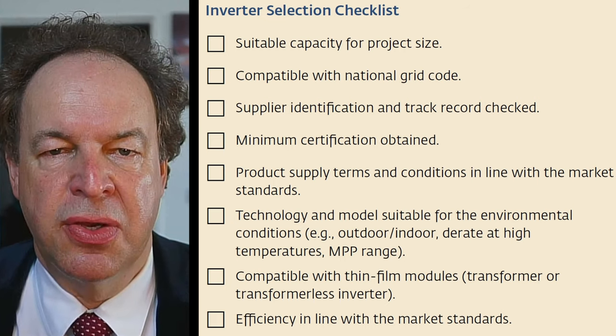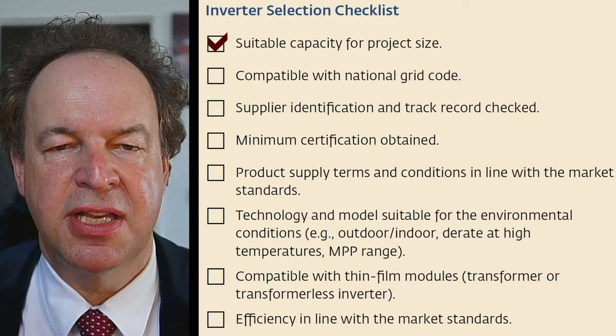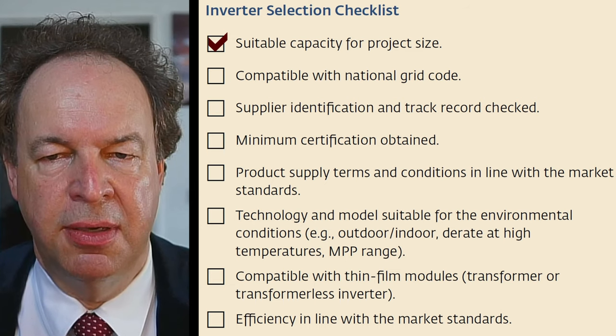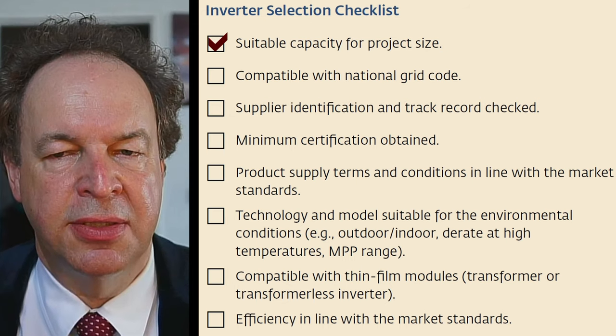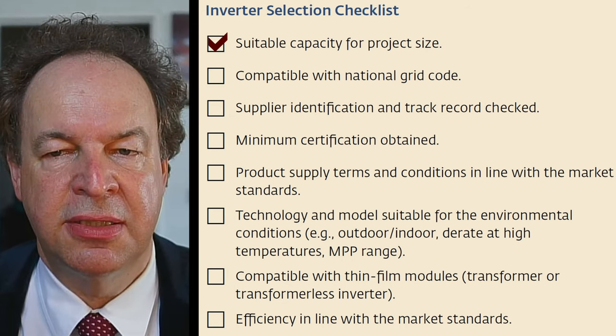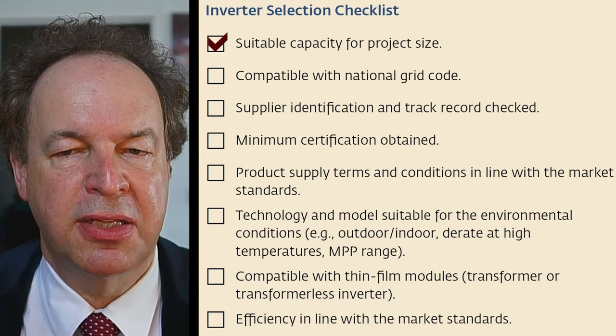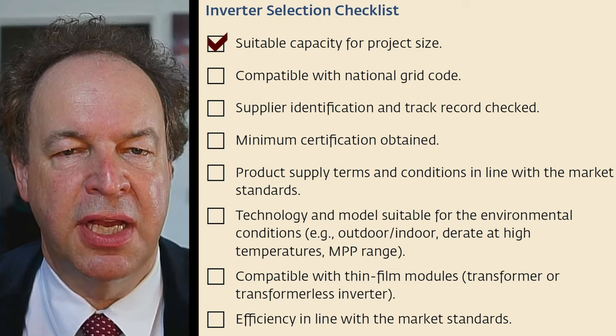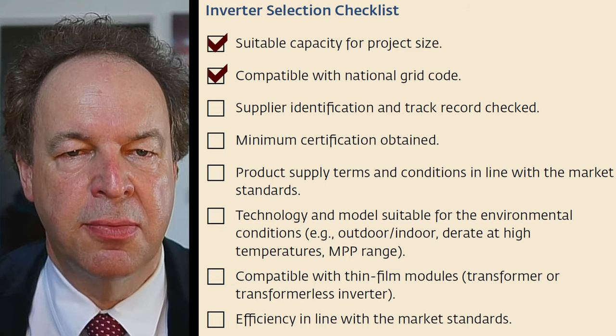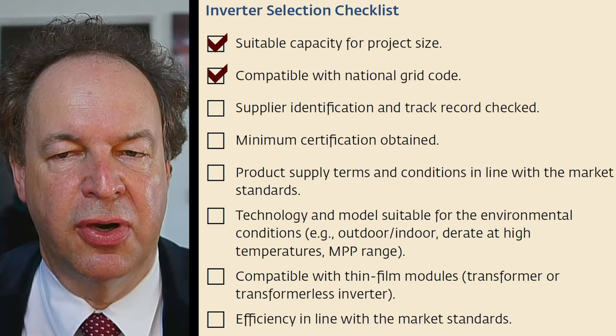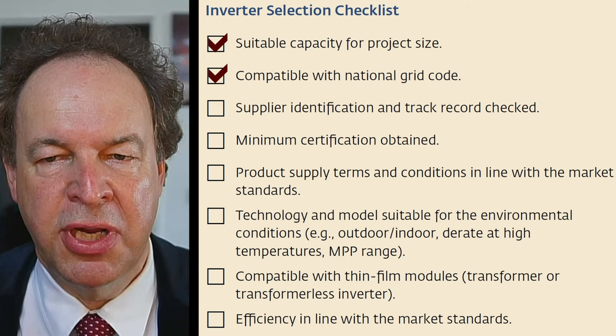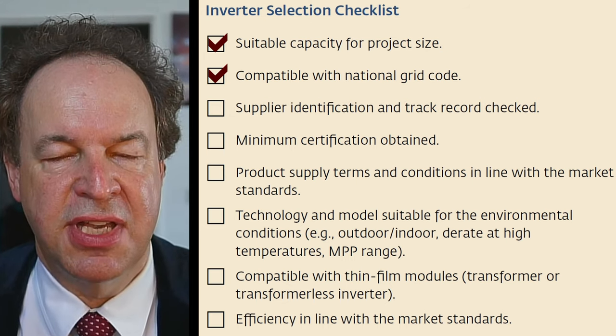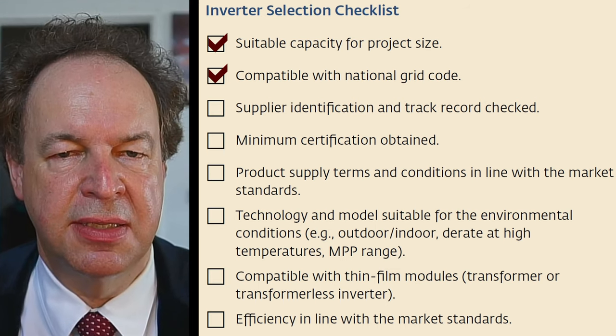Let's come to the inverter checklist. Suitable capacity for the project size — in Europe the modules seldomly achieve the power output under standard test conditions, so you may undersize the inverter a little without many losses. For other countries it's different — you're quite close to standard test conditions, so you have to choose the right inverter size. Every country has its own national grid code, so the inverter has to be compatible and have the correct certificate — this could include fault-ride-through, harmonics, and so on. Whether the inverter can be switched off remotely depends on the project size. This has to be checked in advance and is quite cumbersome.